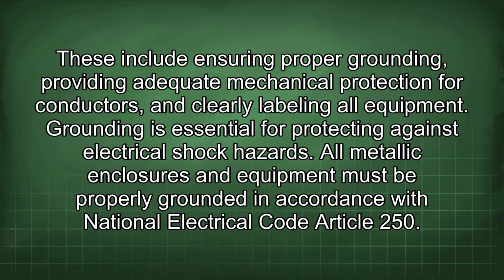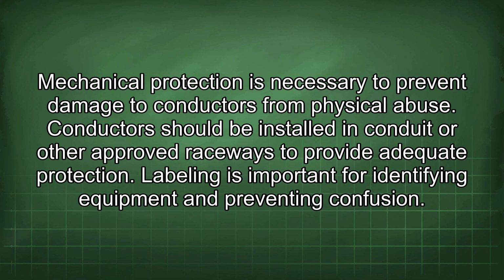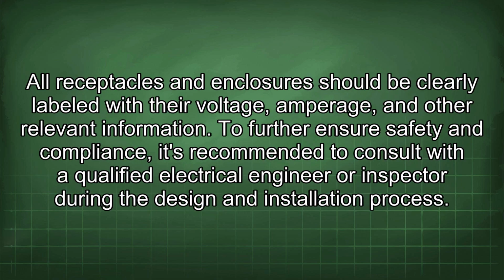These include ensuring proper grounding, providing adequate mechanical protection for conductors, and clearly labeling all equipment. Grounding is essential for protecting against electrical shock hazards. All metallic enclosures and equipment must be properly grounded in accordance with National Electrical Code Article 250. Mechanical protection is necessary to prevent damage to conductors from physical abuse. Conductors should be installed in conduit or other approved raceways to provide adequate protection. Labeling is important for identifying equipment and preventing confusion. All receptacles and enclosures should be clearly labeled with their voltage, amperage, and other relevant information.